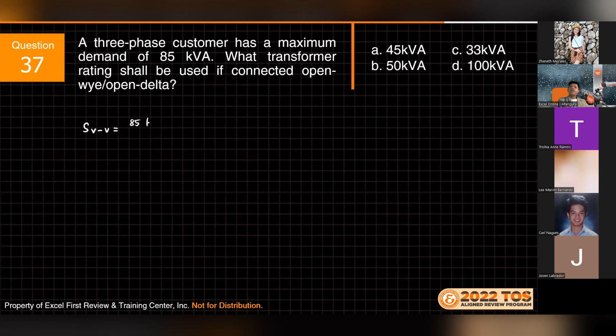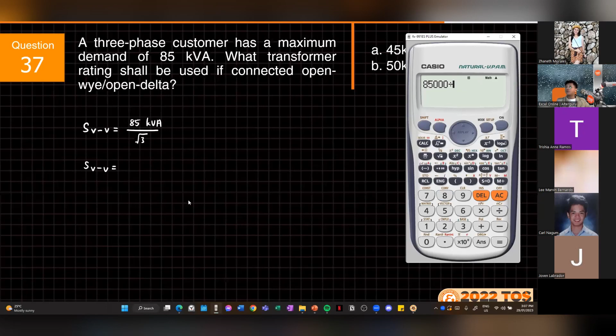Ang S open delta natin is yung S ng 3-phase na 85 kVA divided by square root of 3. So ang S natin ng open delta becomes 85,000 over square root of 3, we have 49.075 kVA. Ito yung transformer capacity.